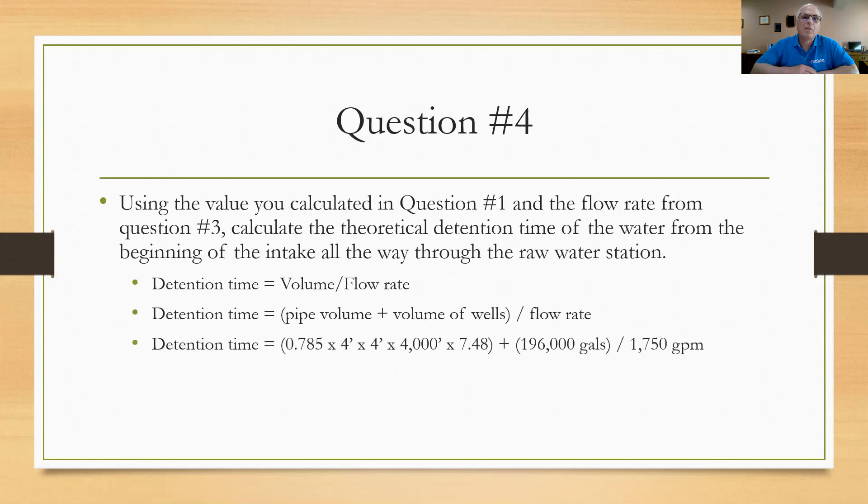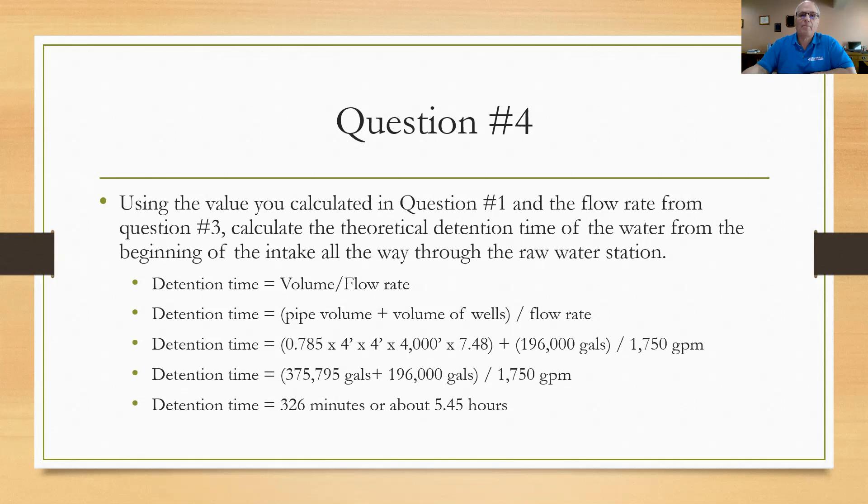So the detention time is going to become this: 0.785 times 4 times 4 times 4,000 feet. That's how long the intake is and I convert that to gallons by multiplying by 7.48. I'm going to take that value and add it to the volume of the wells that I already calculated which was 196,000. Add those two together and I can divide by the 1,750 gallon per minute rate. So the detention time becomes 375,795 gallons plus the 196,000 gallons divided by 1,750 gallons per minute or about 326 minutes which is roughly 5.45 hours. That's a long time. You can see that when the water moves that slow it creates a lot of detention time. Makes sense.